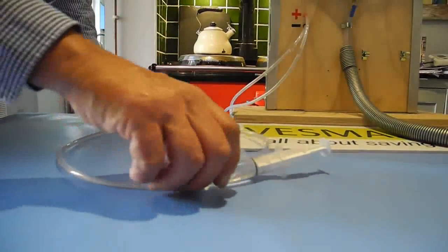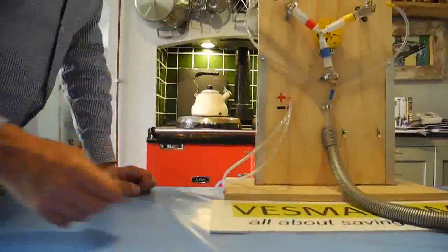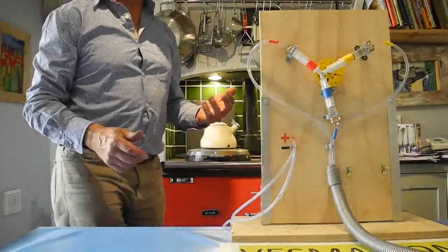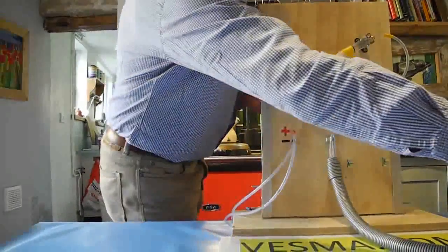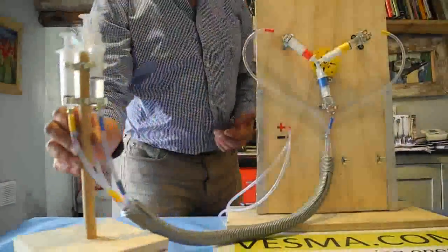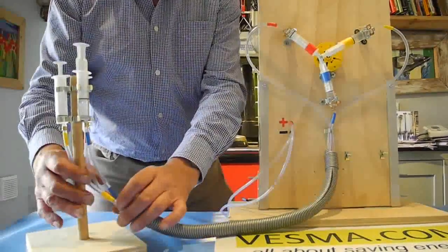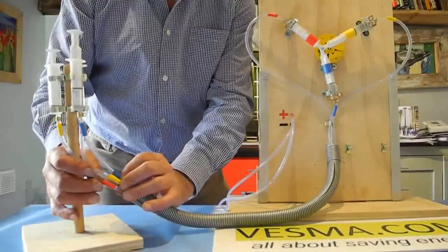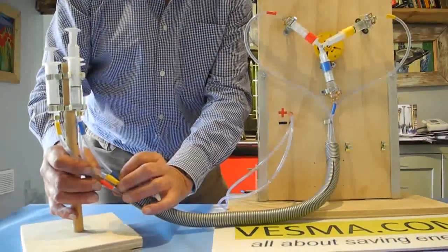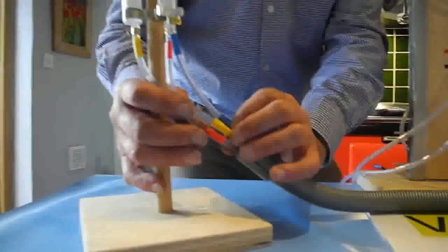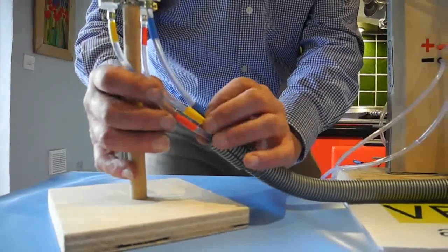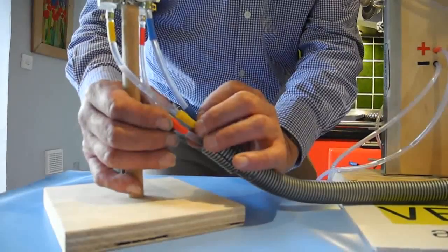But for large buildings, because of the need to deliver more power and also to match the way that the public electricity supply works, the electricity comes into most substantial buildings through 3 wires. Now, the important thing to understand is that all 3 of these cables are live. So you could get a fatal shock from any one of them. They're all live, in a sense they're all the same, and we designate them as red, yellow and blue.